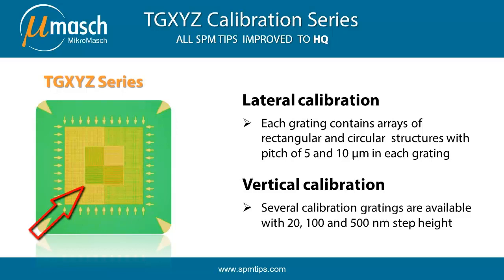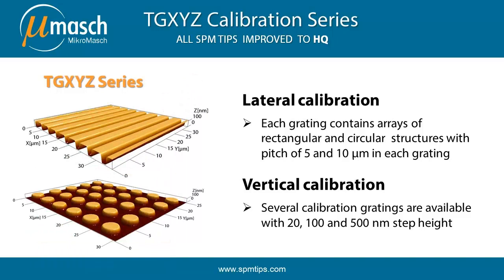The smallest square in the center includes circular pillars and holes, as well as lines in X and Y direction with pitch of 5 microns. The larger square contains square pillars and holes with pitch of 10 microns. AFM topography images of the pillars and the lines with 5 microns pitch are presented here. These structures are convenient for accurate X, Y and Z calibration of the scanner.